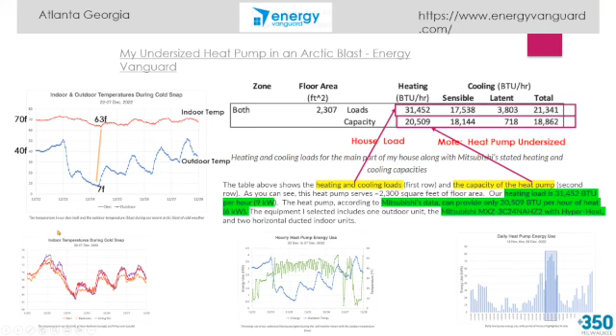So does it perform when it's needed? Does it keep all the rooms in a reasonable temperature range? This one is showing hourly heat pump energy use. I love this, because here's the temperature curve, the same curve as before, but now it's showing how hard the heat pump was working in order to keep, during this time period, the 60 degree Fahrenheit. This is crucial stuff, folks.